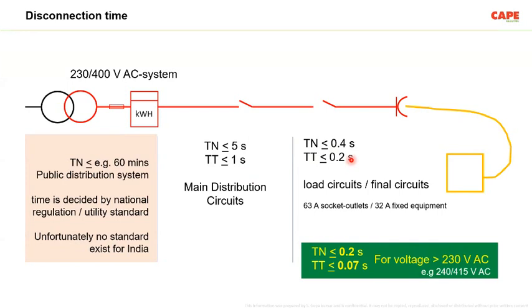But when we talk about electricity supply companies, a big discussion starts. They say our supply is not 230, it is 240. Yes, of course, if your supply is 240, then the disconnection time is even smaller. In case of a 240 volt supply, the TN system disconnection time is 0.2 second and TT is 0.07 second. So defining the voltage carries a little bit of risk here.